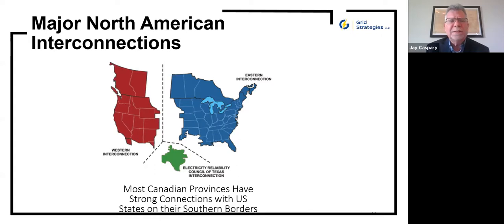Back in 1967, they tried to synchronize the Eastern and Western grids, but it wouldn't stay together because the thermal mass and unit sizes in the East were about four times those in the West. Any outage in the West caused 80% of the energy to flow from East to West to restore balance, tripping relays and lines. So they installed DC ties that have been there since the 70s, and we'll probably need to figure out what to do with those long term.